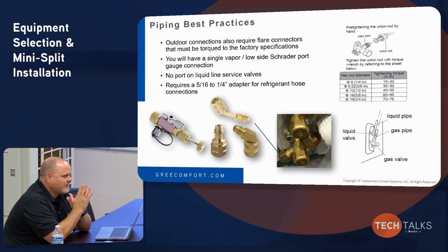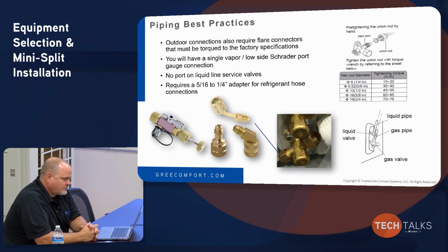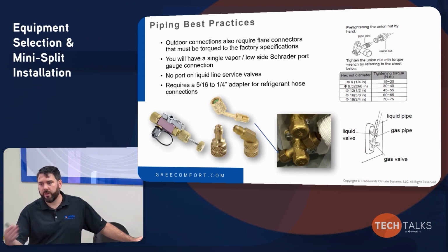Good explanation. Keep in mind that the metering device on all the ductless mini splits, that EEV or cap tube, some of them are just a cap tube, is in the outdoor unit. Right. So it's not like traditional units. It's still an air conditioner, it's still a heat pump, but the biggest difference is that the metering device is outside. That's why both lines have to be insulated, because in the summer months they're both low side, and in the winter months they're both high side. So that essentially makes our line set an extension of the evaporator. That's why we have to insulate both lines, so that we don't have condensate dripping.